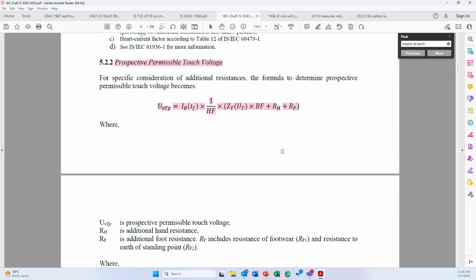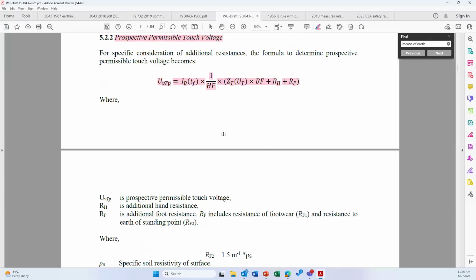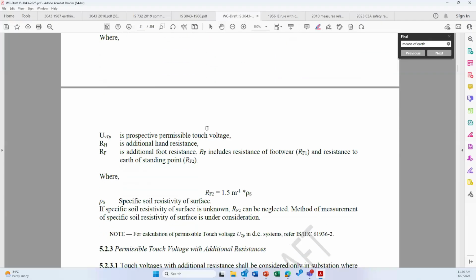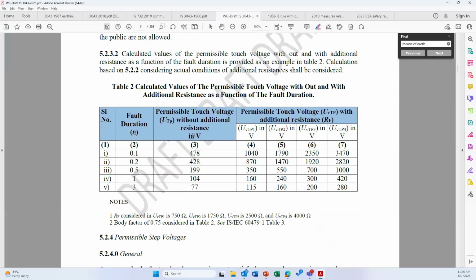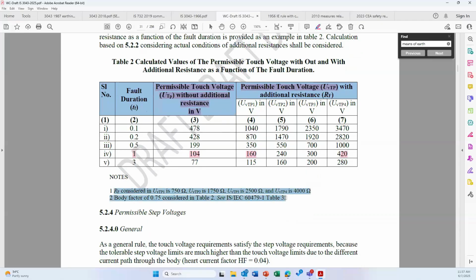Please note that this information was already existing in IEC 61936. So when you read clause 10, you also should read together with clause 5.2. The prospective permissible touch voltages are given here. Let's say, for example, 1 second tripping time, the permissible touch voltage is 104 volt. Then the permissible touch voltage with additional resistance, let's say with gloves or with shoes, 1 second disconnection, in a typical case 160 volt or 420 volt, you can find out. You see the conditions are given here.